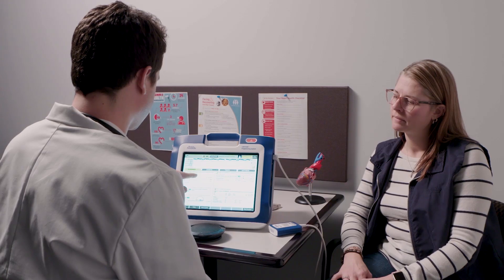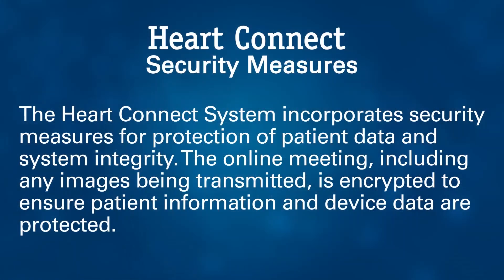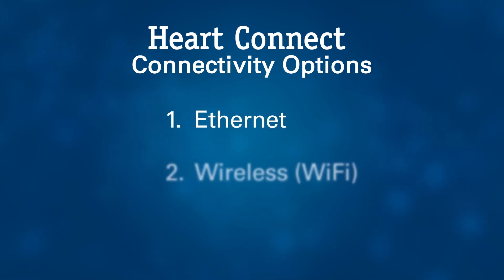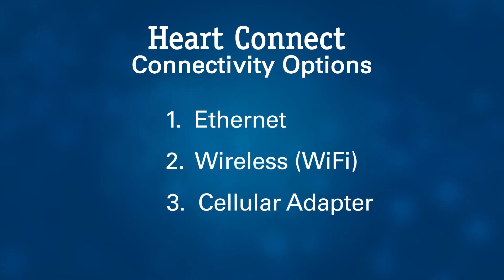The HeartConnect system incorporates security measures for protection of patient data and system integrity. The online meeting, including any images being transmitted, is encrypted to ensure patient information and device data are protected. There are three network connectivity options: Ethernet, wireless, and cellular adapter.